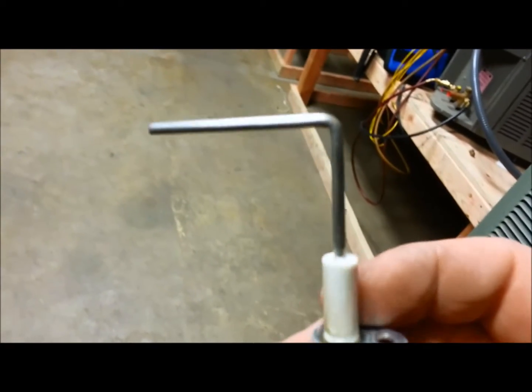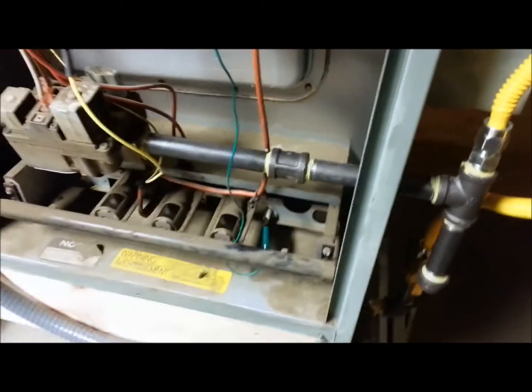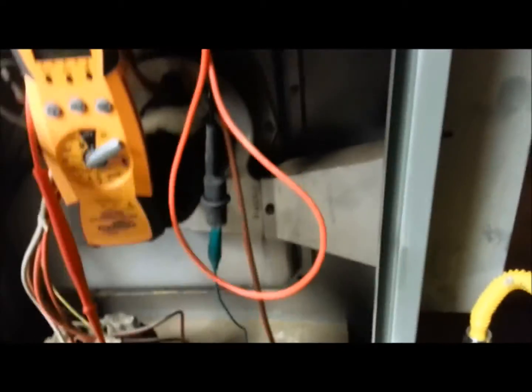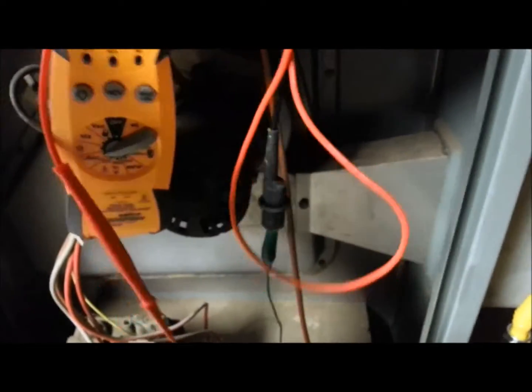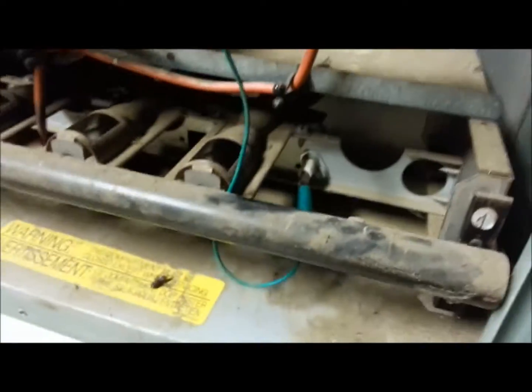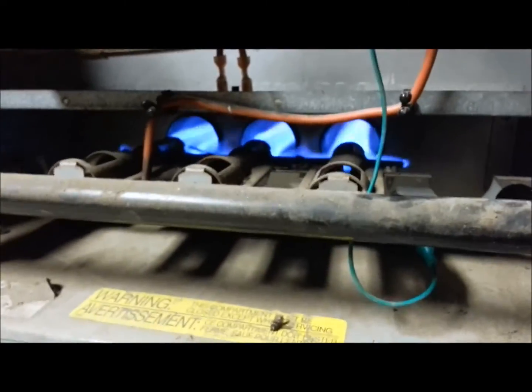Okay, we have the flame sensor polished, put back in, everything's plugged in. Blower motor came on, see what kind of reading we're gonna get out of this. I've got the flame sensor back in place, jumper wires just going through the meter, burners ignited.